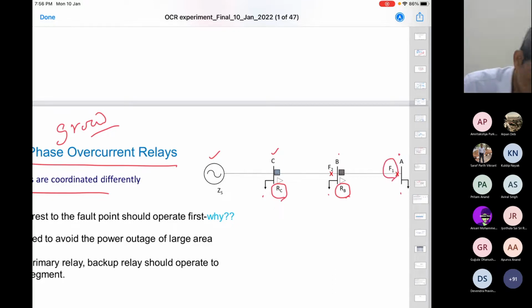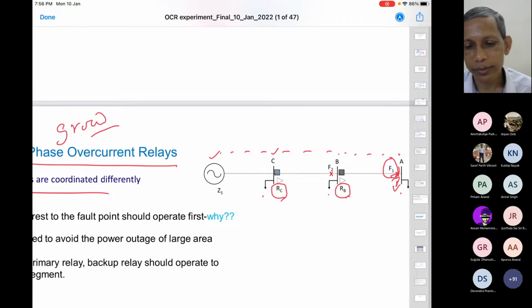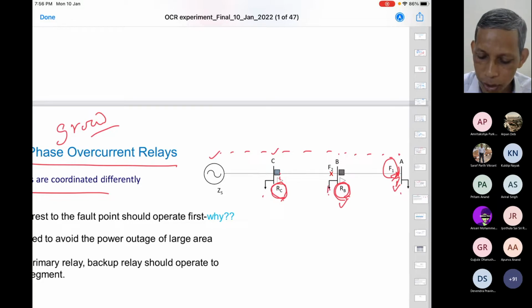If you require clarification, I will explain what coordination is, which you should understand. For this F1 fault, current will flow along this path. This relay will see the same current, and this relay will also see the same current. Both will see the same current. But which one should trip? If RC trips the breaker here, the loads to the right will be affected. From the selectivity point of view, which we were discussing earlier, RB should trip for this F1 fault. Then only this portion will be out of service till the fault is removed. So this load can still be fed from the source side. That is selectivity. Therefore, for F1, RB should trip.